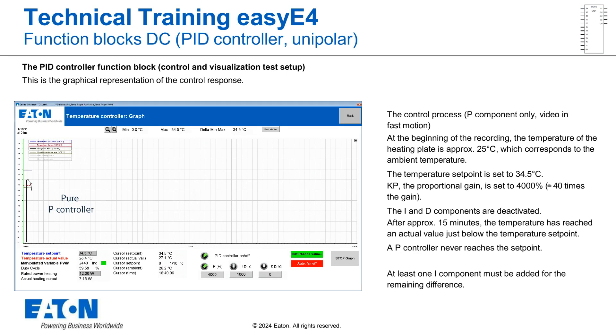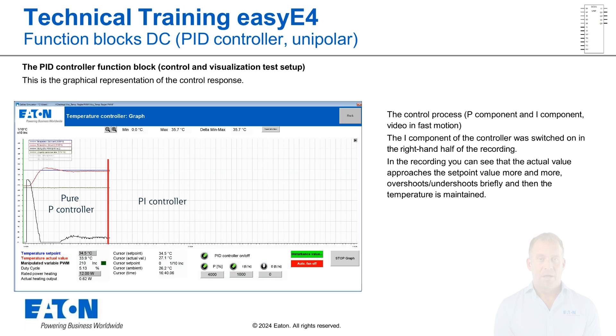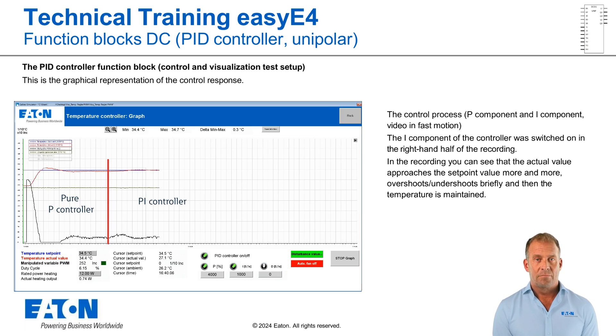At the beginning of the recording, the temperature of the heating plate is approximately 25 degrees Celsius, which corresponds to the ambient temperature. The temperature setpoint is set to 34.5 degrees Celsius. KP, the proportional amplification, is set to 4000%, which corresponds to a 40-fold amplification. The I and D components are deactivated. After approximately 15 minutes, the temperature has reached an actual value just below the temperature setpoint. A pure P controller never reaches the setpoint, which is why at least one I section must be added for the remaining difference. The I section of the controller was switched on in the right-hand half of the recording. You can see that the actual value continues to approach the setpoint, overshoots, undershoots briefly, and then the setpoint temperature is maintained. The parameters were determined empirically, and applied to this specific operating point. Other operating points require an adjustment of the control parameters, and the parameters of more complex controlled systems must be calculated and/or determined using simulations.